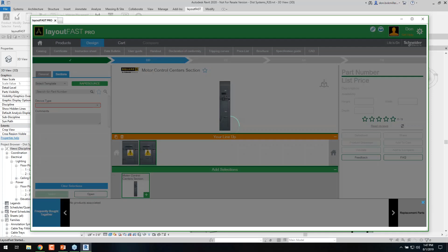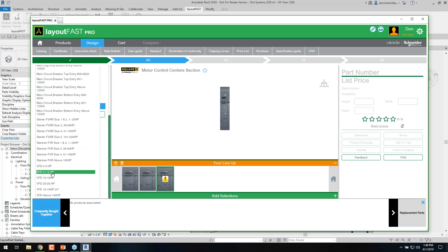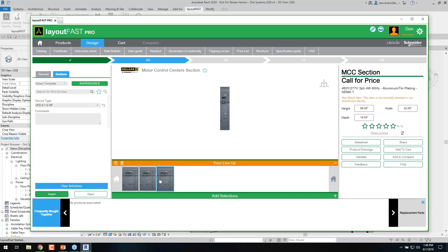Now down here are my choices for sections, which with motor control centers is basically just one section. But let's say it's got 3 of them, so I click that 3 times to add 3 sections. Now it's wanting more information about each section. If I click on that first one, it asks what's going on inside that section. I'm not defining bucket 1 has this and bucket 2 has that, just kind of defining the basic gist of what this section is for. So maybe this is my main circuit breaker section, and then this one's going to be starters that go from 1 to 25 horsepower, and this section here is going to be VFDs. I'm just giving it a general idea of what's happening, not defining what's going on specifically internally.